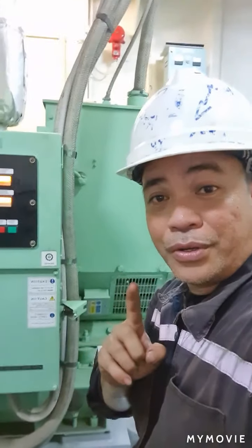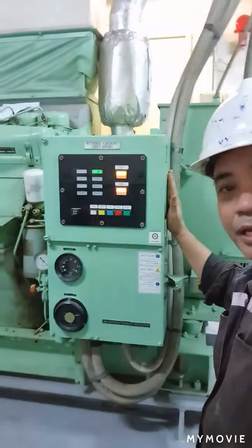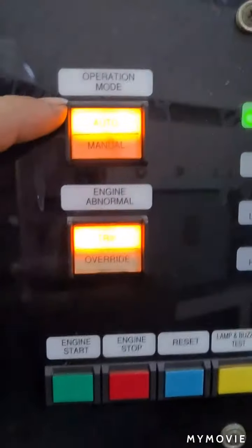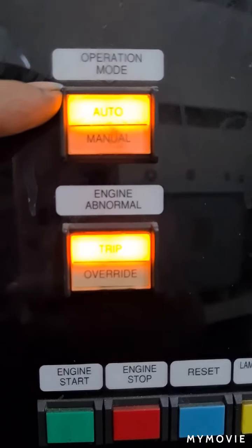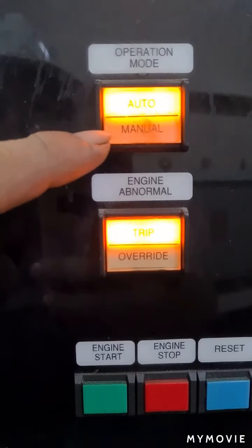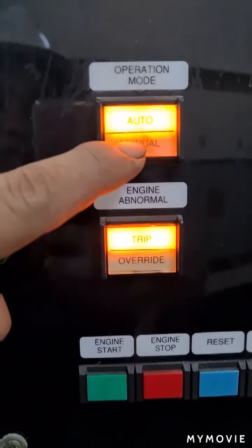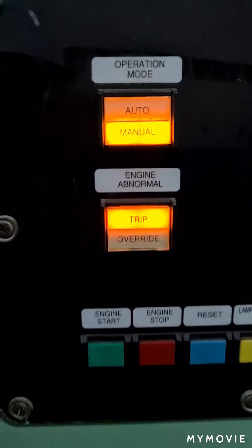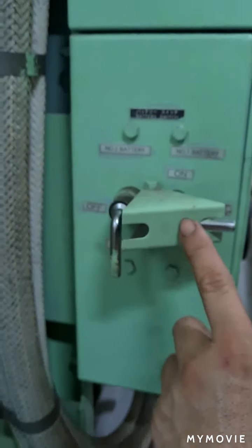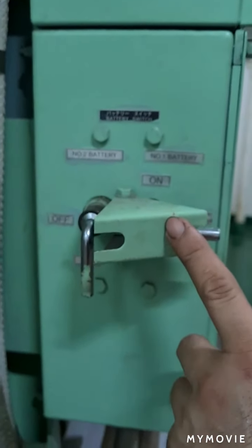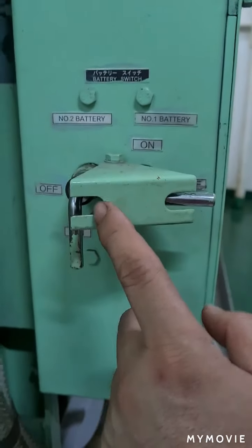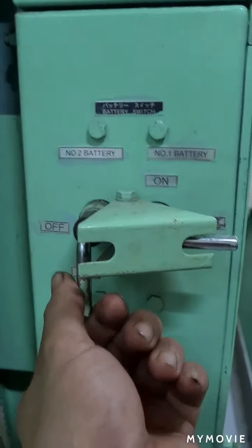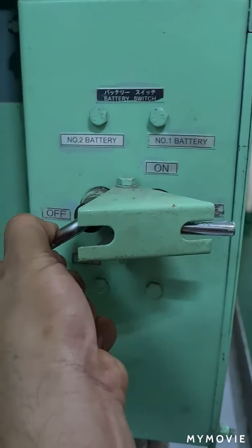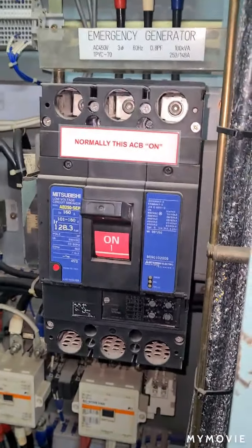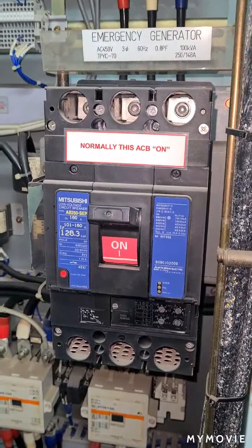As I mentioned before, this is the control panel of the emergency generator. You must bring it to manual mode by pressing this button. Then, this is the battery switch. Both battery switches must be switched off, making the emergency generator switch off.